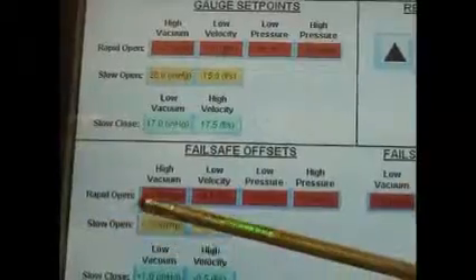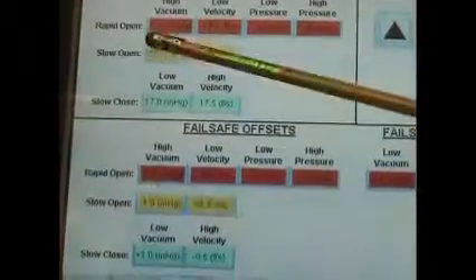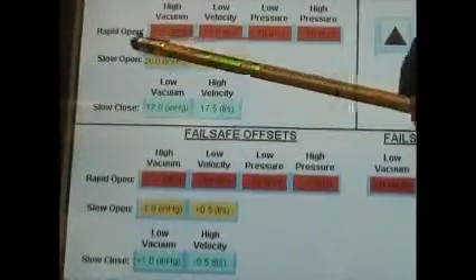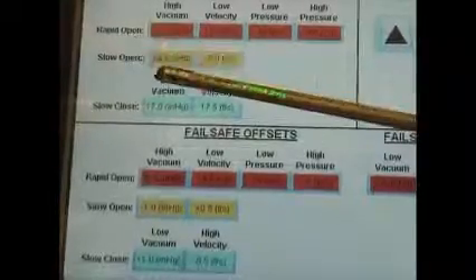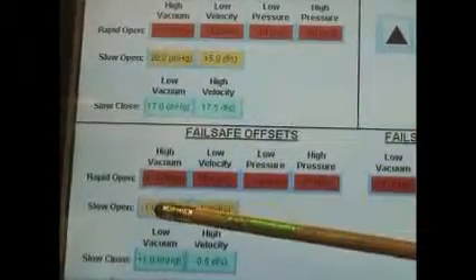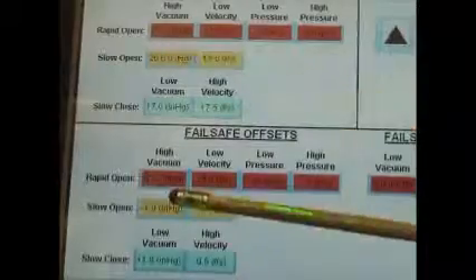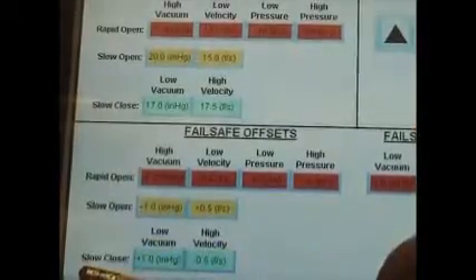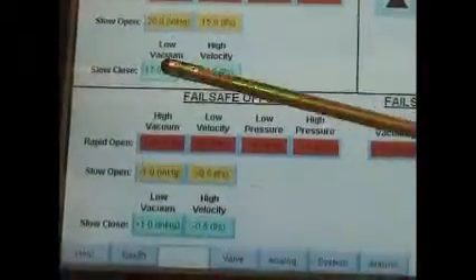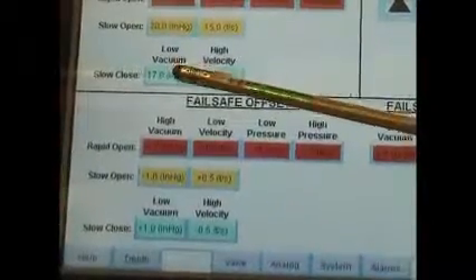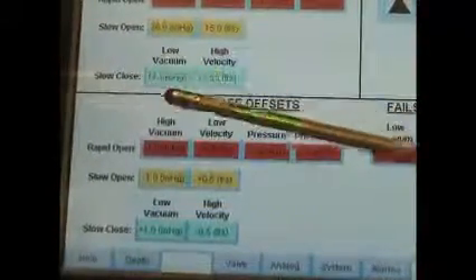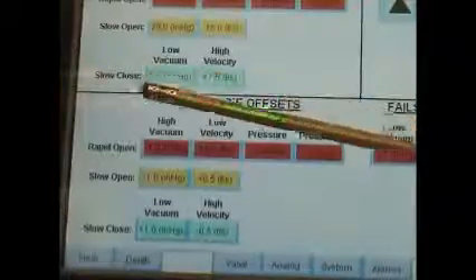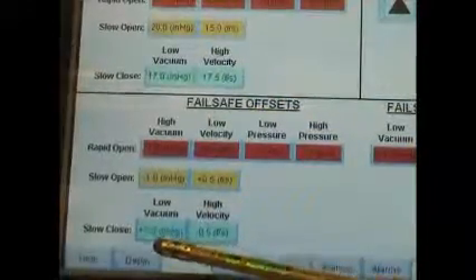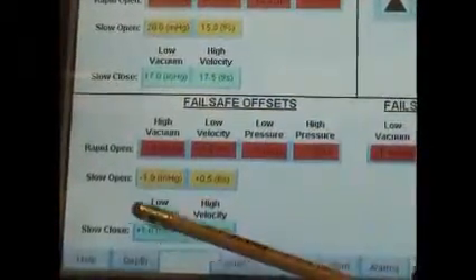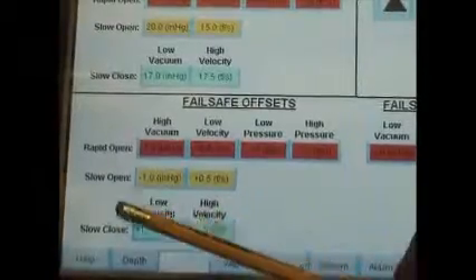Our slow open is going to also be reduced by 1. So right now our valve is going to start to slowly open itself at 20. In this case, it's going to open up at 19, 1 less. And our slow closed, or the area from our green zone and turquoise areas, currently is set at 17, and this is going to increase to 18. It's going to be an additional 1.